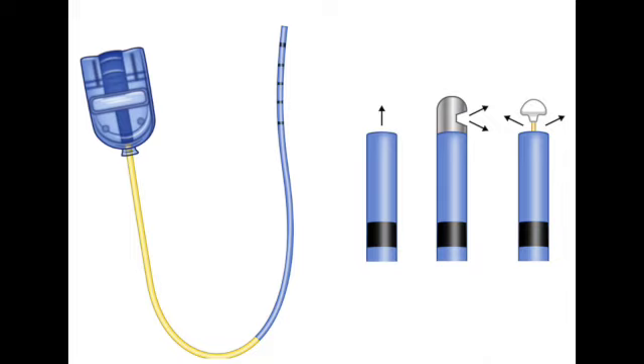Okay, you mentioned monopolar current. That means we need a return path for the electricity. What's the external setup required? Yeah, absolutely essential part. The neutral electrode, or what most people call the grounding pad or dispersive pad, has to be placed on the patient, usually on a large muscle mass like the back or thigh. Why there? It provides a large surface area for the electrical current to safely return to the electrosurgical unit, completing the circuit. Without that pad, or if it's not placed properly, the system won't work right, and worse, the current might try to find another way out, potentially causing burns elsewhere. It's a critical safety step. Right. Completes the loop safely. Now, the delivery catheters themselves, Dr. Raju mentioned 3 types. Seems important to pick the right one.